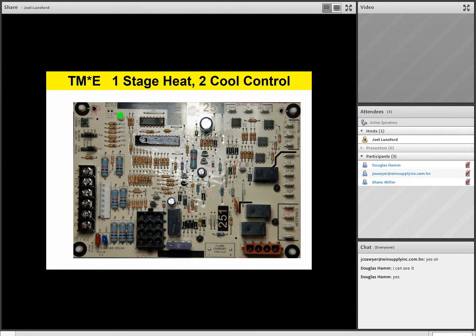They're 24-volt commands from the board to the selected low cool speed on the motor, or the selected high cool speed on the motor, and so on. So this is an important thing about the ECM motor we need to remember as well: it has power to it all the time. Anytime you have power to the furnace, that ECM motor is powered up. And then we send 24-volt commands to it to tell it what to do. Are there any questions on that?